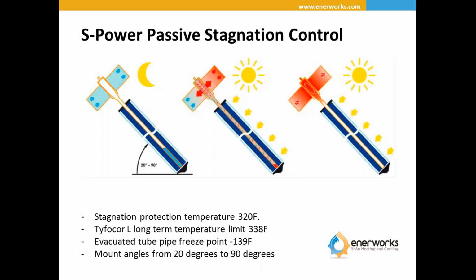How our vacuum tube works, there's actually two vacuums. If you take a look at the first picture on the left, the blue absorber is actually inside a glass tube. There is a vacuum in the glass tube. That vacuum is designed to prevent heat from escaping through the glass. Glass is a great transmitter of thermal energy, and so the vacuum is a perfect insulator. It doesn't allow much, if any, of that heat to leave. The second is there is a vacuum in the copper tube that goes into the manifold.